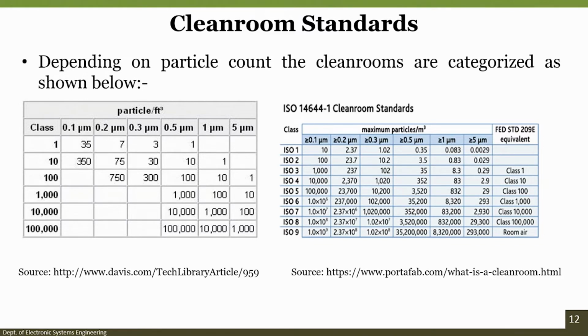That means if you go to a clean laboratory and the air that you find is hopefully clean, you can give the laboratory ISO 9 certification in terms of class. But when you want to create a clean room, you have to make sure that the particle count falls within these particular parameters, so as to make sure that the chip is not deteriorated and the contaminants are minimum.